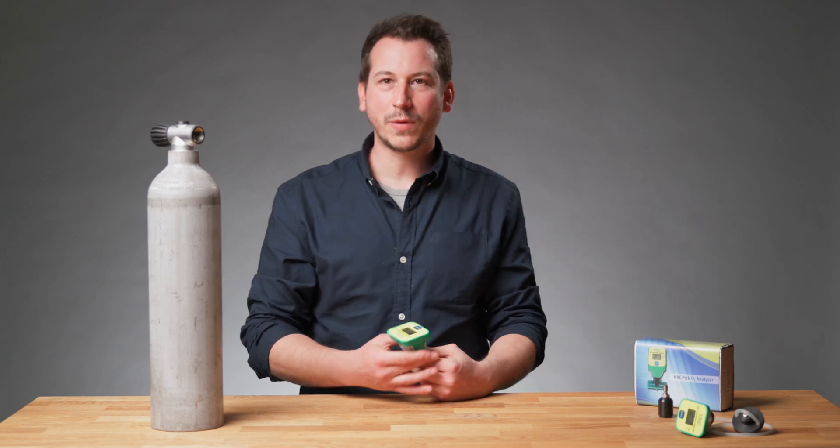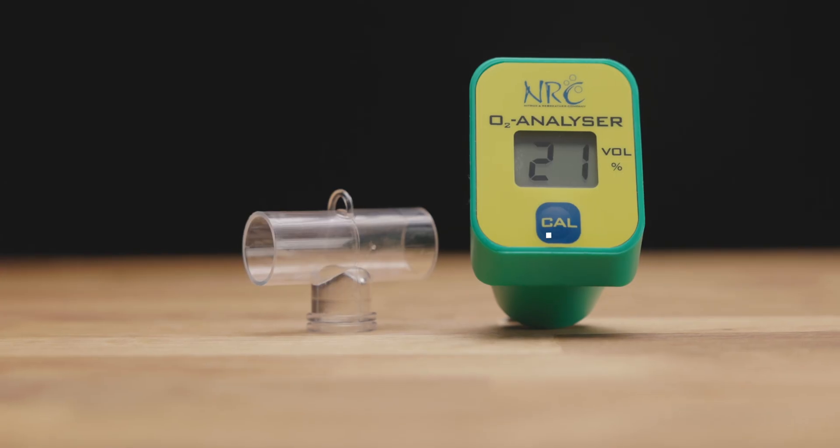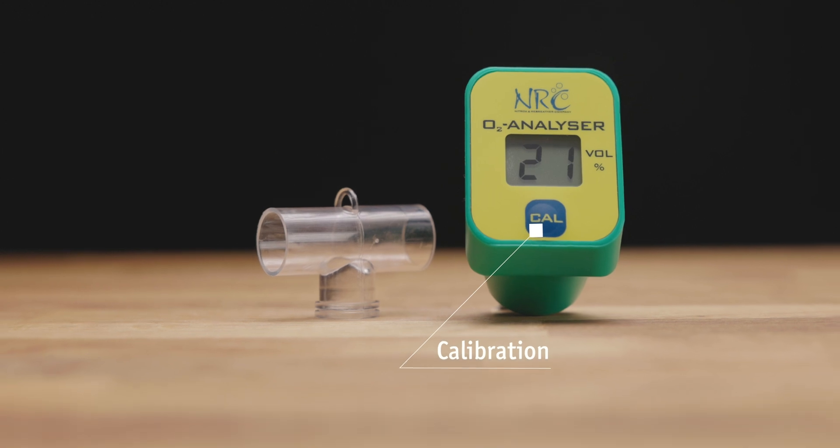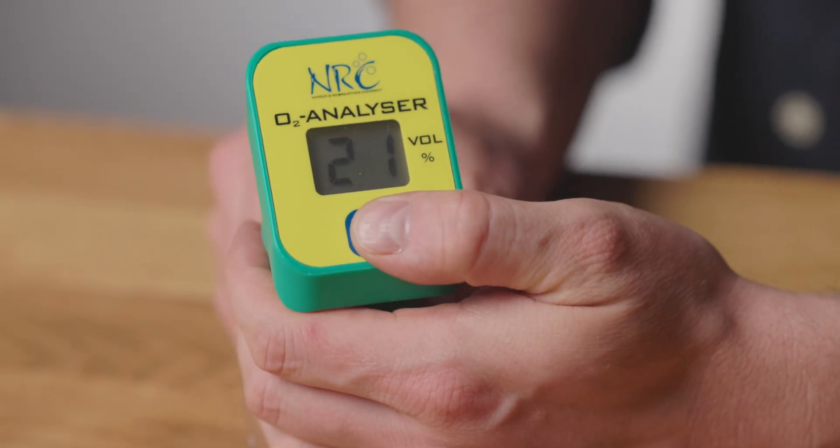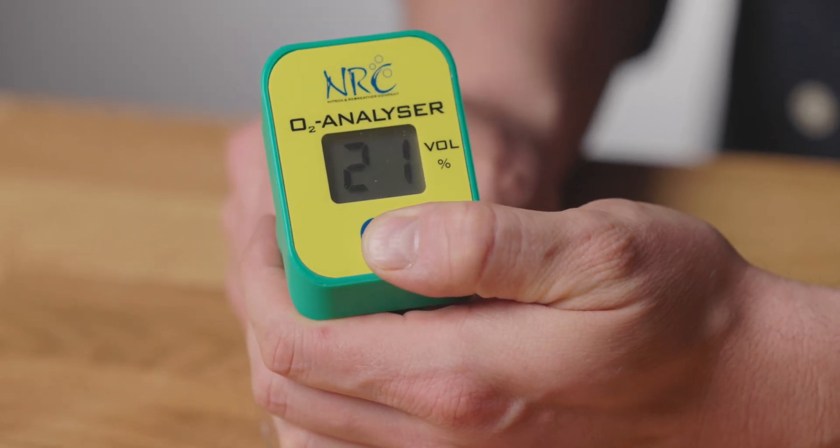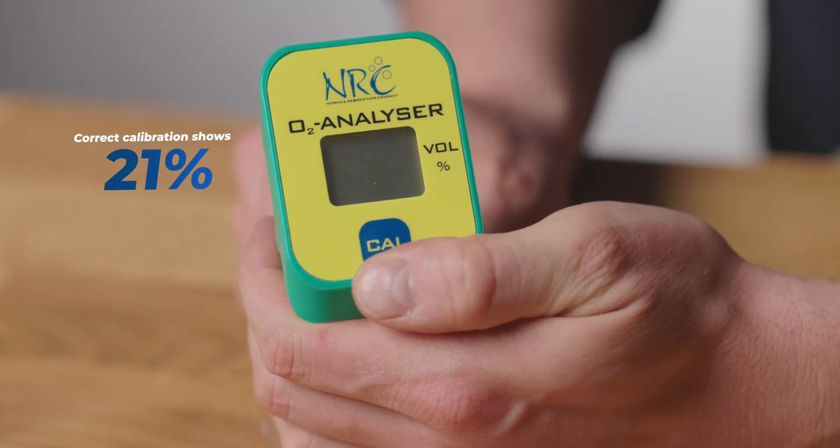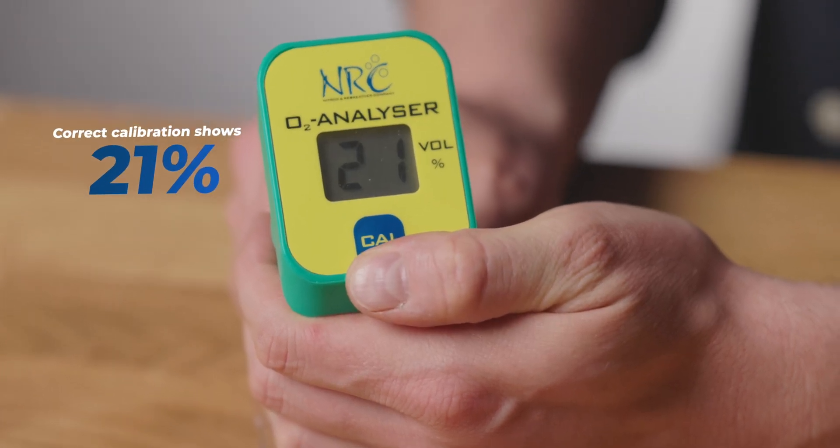First of all, we need to do the calibration of the analyzer. For this we have the calibration button in front of the display. This one we hold for a couple of seconds until the CAL is showing up on the display. And after he shows us the 21% volume.